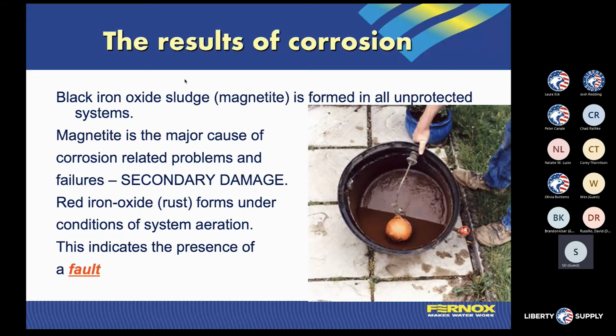Obviously on the black iron side, or the steel piping side, we end up with a byproduct called black iron oxide, or you might have heard the term bio. So bio barriers for pumps and different things of that nature, seals, and magnetic filters, which we'll talk about today, get into a lot of the black iron oxide components. That is essentially the breakdown of any of the steel components in the system, whether that is galvanized, straight steel, or cast iron.